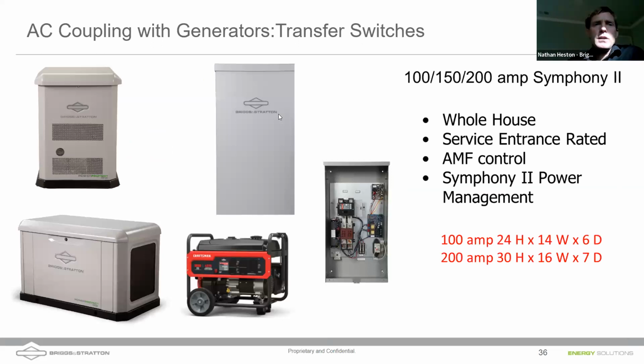If you're using AC coupled solar with generators, it's important that you understand the capabilities of the transfer switches as well. And you'll need to make sure that the inverter is capable of taking both of those in.